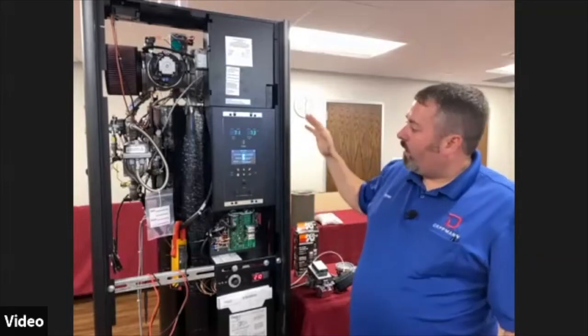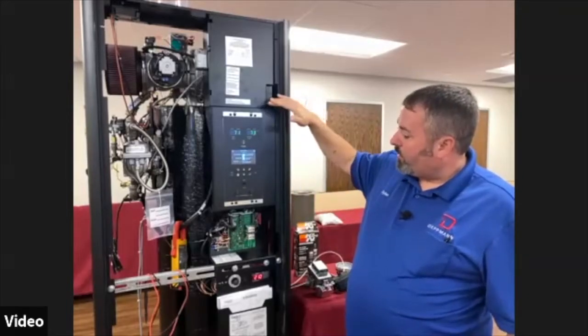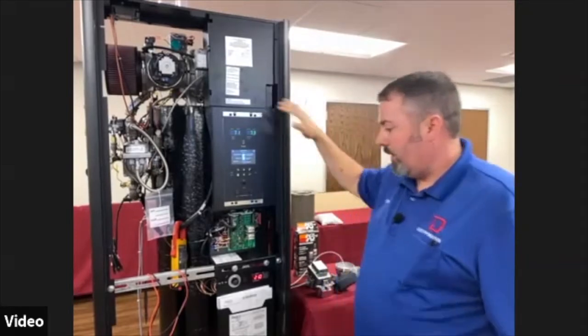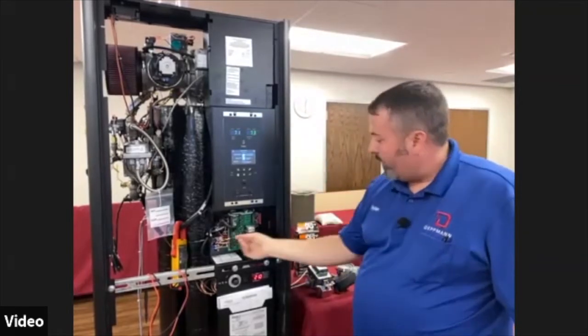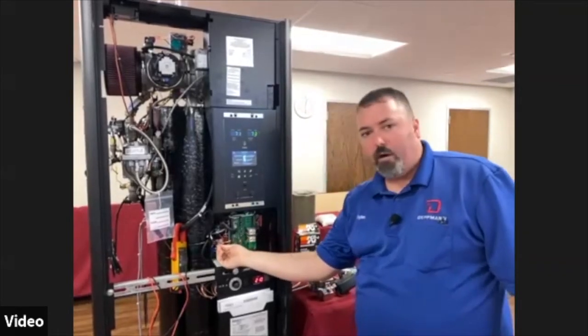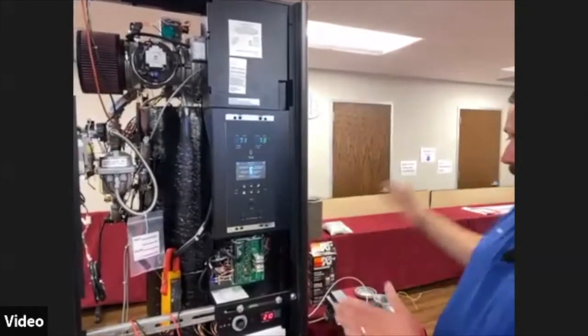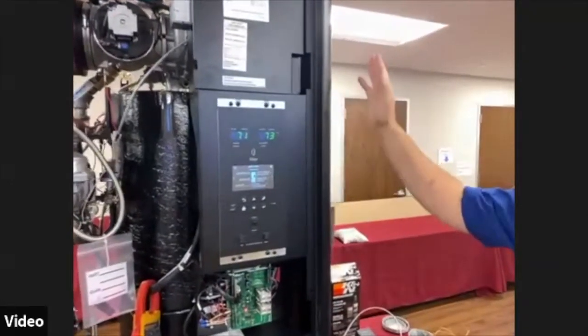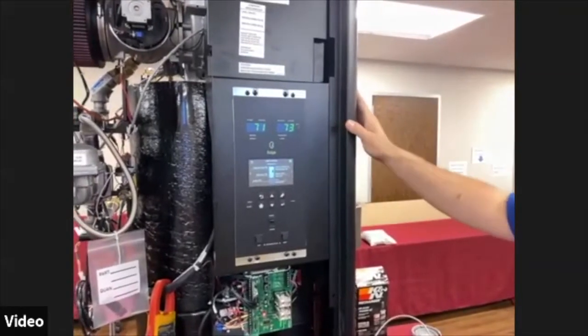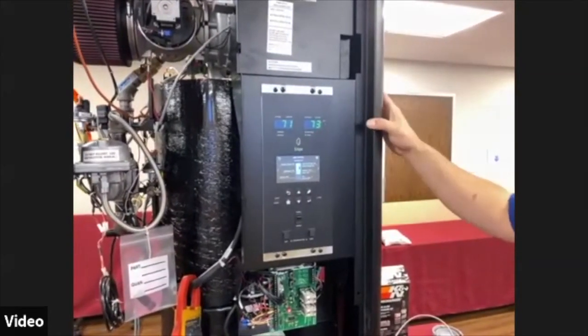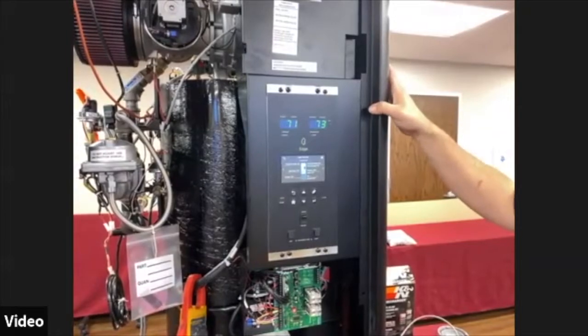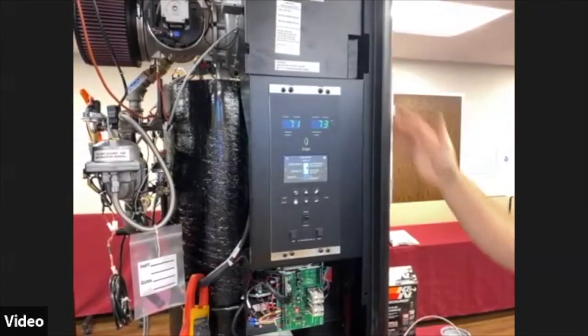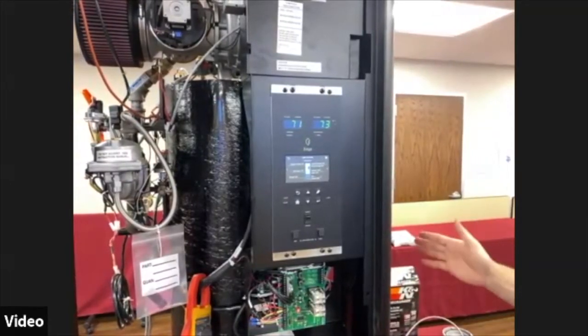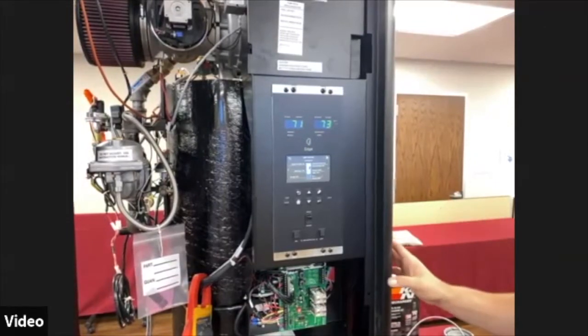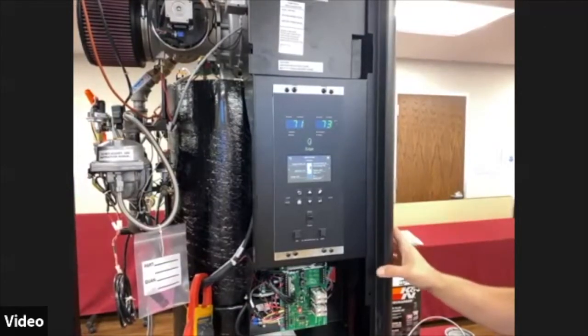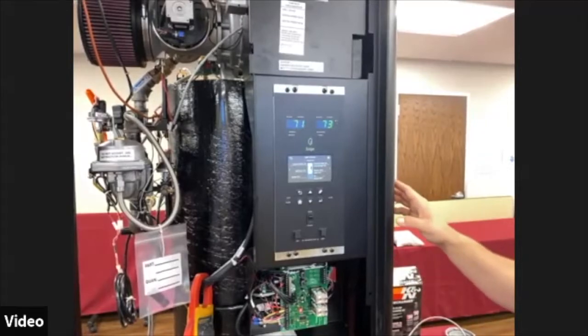From there, I'm going to go into how our BST works. If we have multiple boilers, they will be daisy chained, like Ron said, off of RS-485 wires. So you have multiple boilers together. This boiler would be the managing boiler. That's how we would set up. That's where the header sensor and outdoor air sensor would be tied to. The managing boiler will determine which boiler is lead based on run hours. It cycles the lead boiler by looking at everybody's run hours and keeping them even.